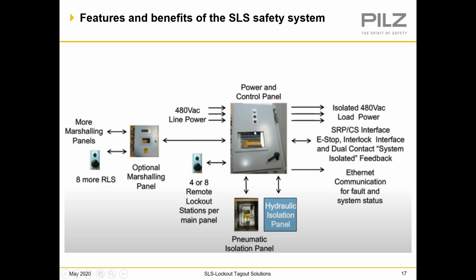And then for each panel, we have configurations for either 4 or 8 remote lockout stations per panel. And if you have a lot of entry points, a larger cell, you can add up to 7 marshalling stations, each of them having an additional 8 remote lockout stations per marshalling panel. So with 7 marshalling panels fully loaded, you have a total of 64 possible remote lockout stations controlling this hazardous energy panel, power through this panel right here.